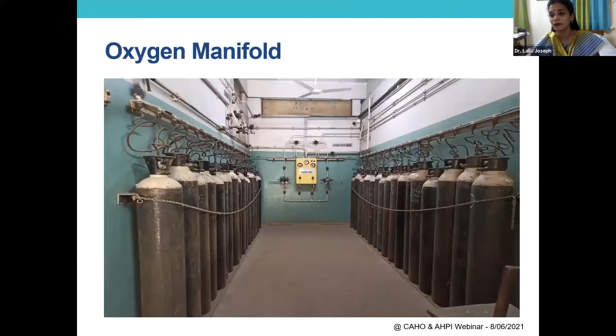This is how our oxygen manifold typically looks. Manifolds become the main supply for small hospitals. And this becomes the first level of backup for hospitals with the liquid medical oxygen. You need to have both the right bank and the left bank completely connected and pressurized. So what is connected to the manifold, we call it the D-type cylinders, which is about 6.7 cubic meter.